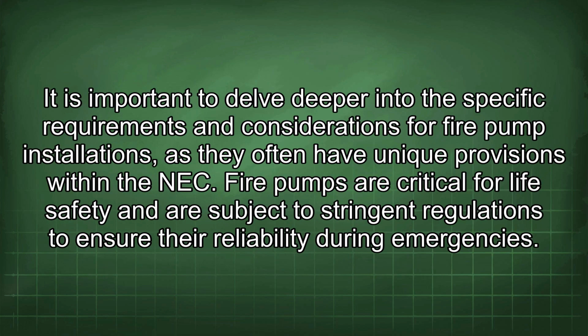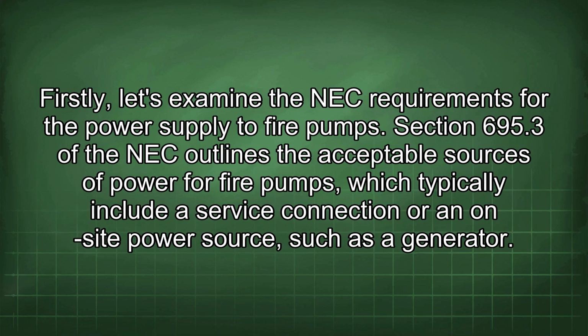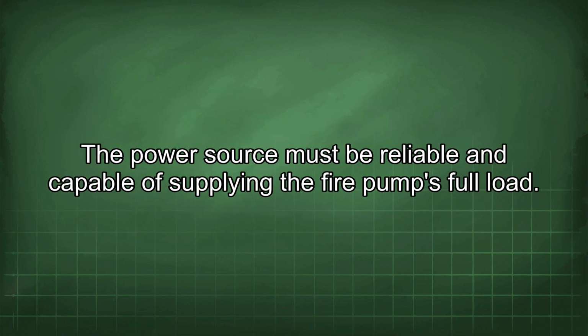It is important to delve deeper into the specific requirements and considerations for fire pump installations, as they often have unique provisions within the NEC. Fire pumps are critical for life safety and are subject to stringent regulations to ensure their reliability during emergencies. Firstly, let's examine the NEC requirements for the power supply to fire pumps. Section 695.3 of the NEC outlines the acceptable sources of power for fire pumps, which typically include a service connection or an on-site power source such as a generator. The power source must be reliable and capable of supplying the fire pump's full load.